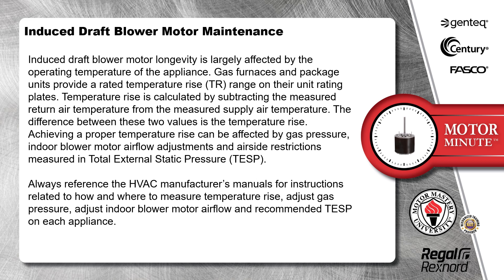Achieving a proper temperature rise can be affected by gas pressure, indoor blower motor airflow adjustments, and airside restrictions measured in Total External Static Pressure, or TESP. Always reference the HVAC manufacturer's manuals for instructions related to how and where to measure temperature rise, adjust gas pressure, adjust indoor blower motor airflow, and recommended TESP on each appliance.